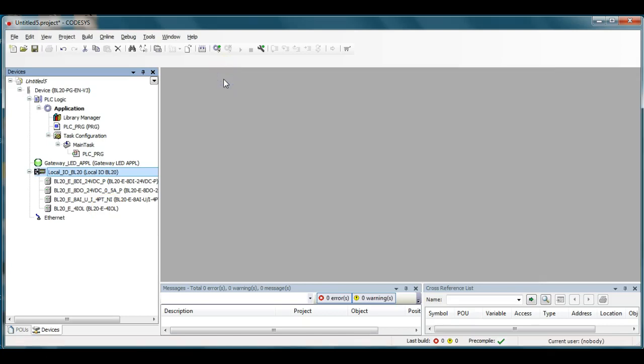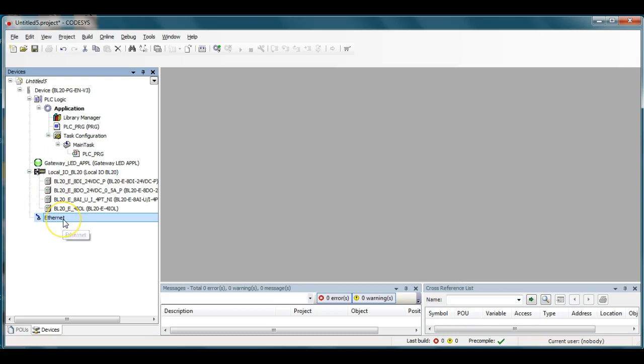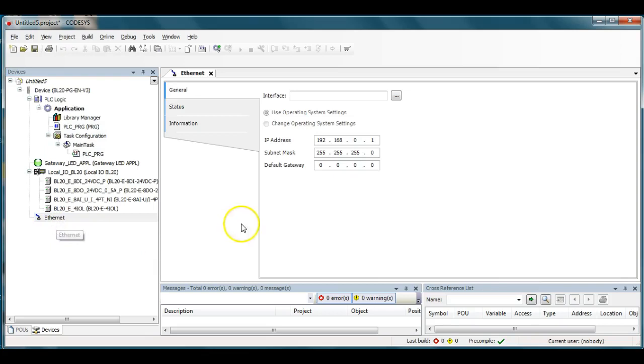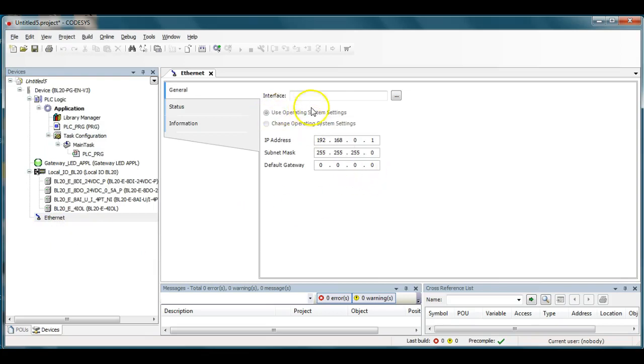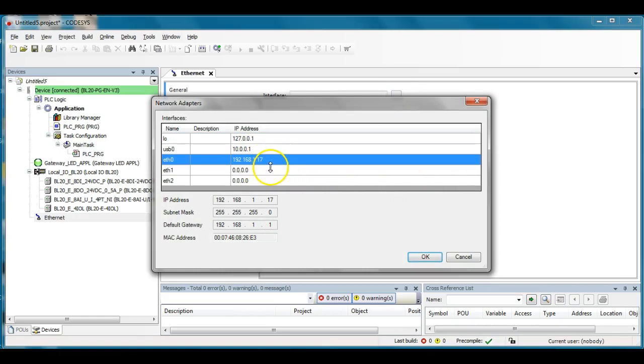So that takes care of setting up my local rack but my goal here is really just to show you guys how to configure this thing as a Modbus TCP slave to have some Modbus TCP master device talk to it. So down here on the ethernet part over here on the left I'm going to go ahead and double-click on this here to pick the interface we're using and that is currently the IP address of my BL20 is 192.168.1.17. So I'll click OK to that.